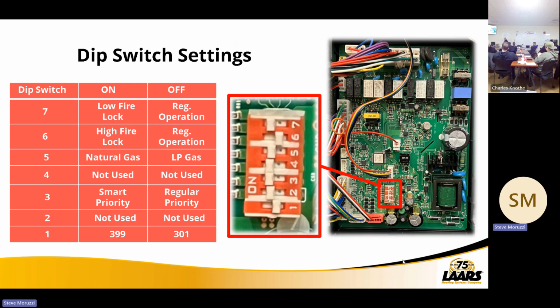That's something that we've talked about, maybe on another revision or firmware change, we may consider that. To your point, maybe in an hour and a half, 90 minutes, come out of domestic mode, go back to heating. Well, I think even 30 minutes they do it on relays now. Example of 30 minutes: you can have a multi-dwelling condo complex, right? We did have this with our Neotherm years ago with Honeywell controls. Let's say there's 12 apartments.